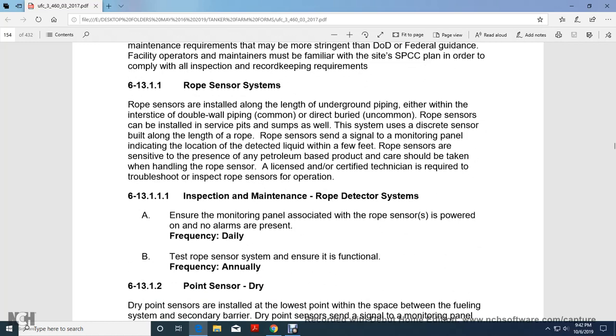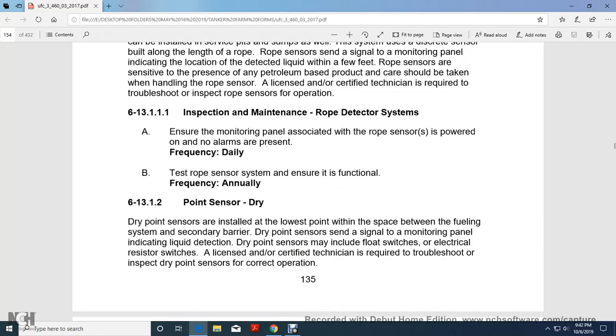6.13.1.1 Rope sensor system. Rope sensor systems run along the length of the underground piping, either within the interstice of double wall piping or with direct buried piping. The rope sensor can be installed within service pits and sumps as well. The system uses discrete sensors built along the length of the rope. The rope sensor signals the monitoring panel to indicate the location of the detected liquid within a few feet. Rope sensors are sensitive to the presence of petroleum-based product, and care should be taken when handling them. A licensed certified technician is required to troubleshoot and inspect rope sensors for operation.